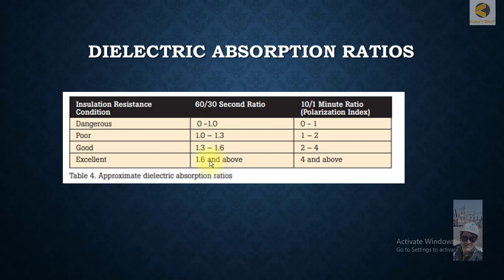For the polarization index, which is the 10 minute to 1 minute ratio, if the reading is more than 4, then it's excellent.